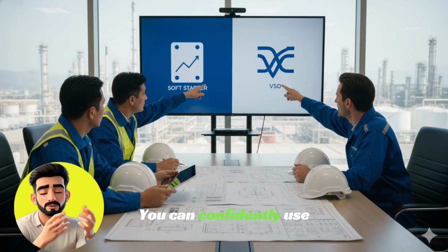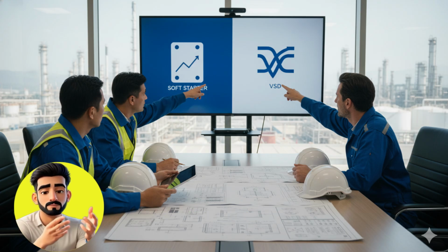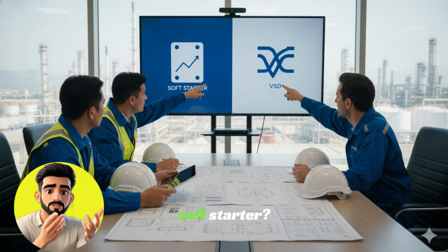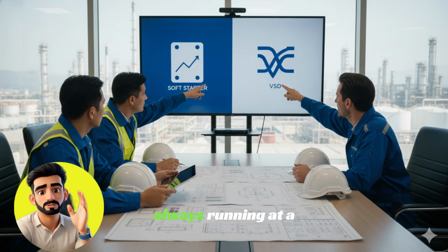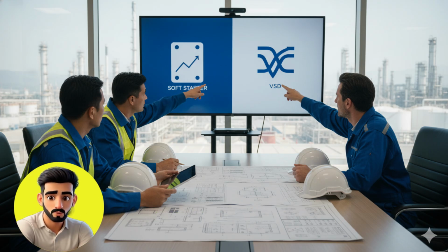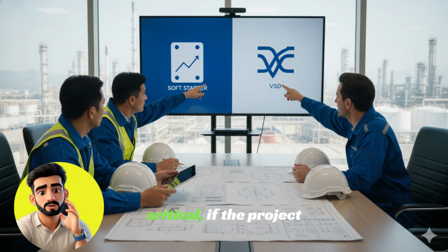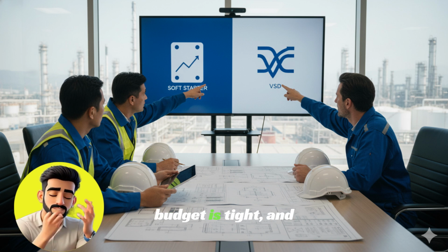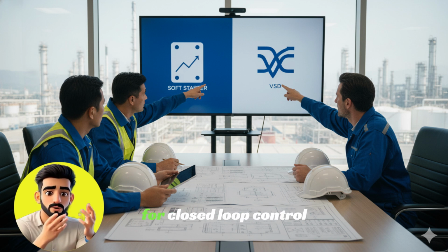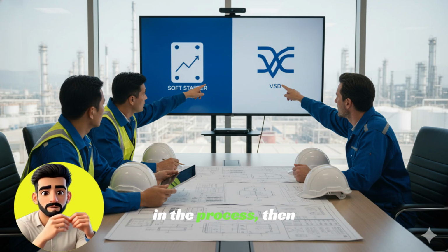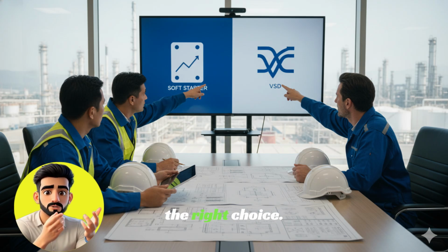You can confidently use this chart in project meetings. First of all, when should you choose a soft starter? If the load is always running at a constant speed, if you only need to control the starting current and want to reduce mechanical jerk a little, if power quality is not critical, if the project budget is tight and there is no requirement for closed loop control in the process, then a soft starter is the right choice.